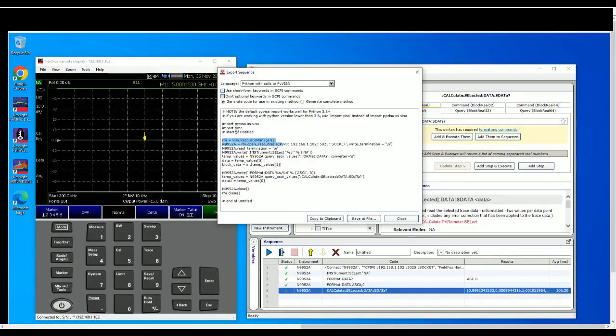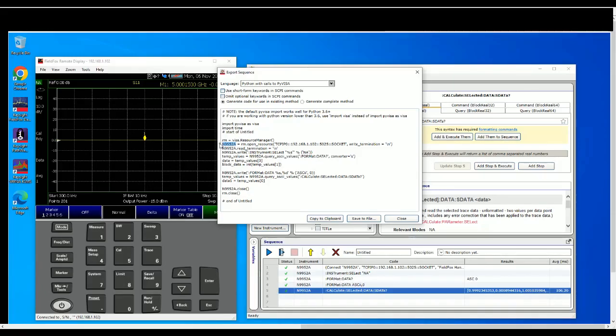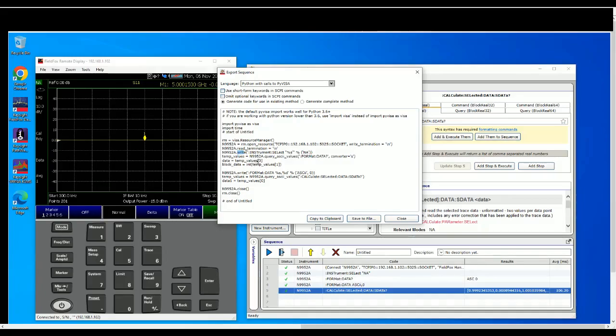So this is the resource manager. You have to import PyVISA, you have to pip install PyVISA prior to using this. Then just copy and paste the whole thing. So this is how it looks like. So from resource manager we're going to declare another instance that ties to this IP address. And from there every time we write means that we are sending the instrument SCPI command. And then every time we query, this is how we query, get back the data.